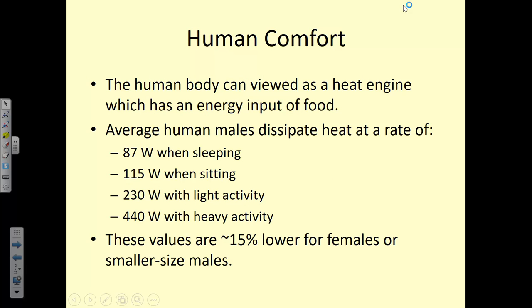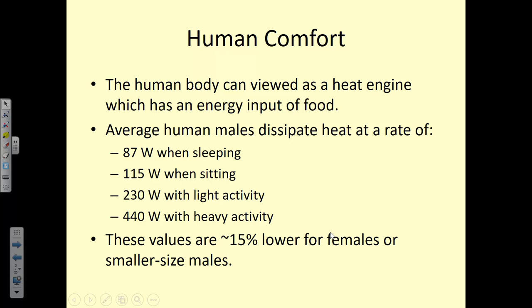When we talk about air conditioning, it necessitates a discussion of human comfort. If we think about our bodies, we intake food, water, we excrete, but we also have waste heat. So we can look at ourselves pretty much like a heat engine, where we're consuming and depositing heat to a heat sink. The average human male dissipates heat at 87 watts when sleeping, 115 when sitting in class, 230 with light activity like golf or bowling, and 440 with heavy activity like running or lifting weights.